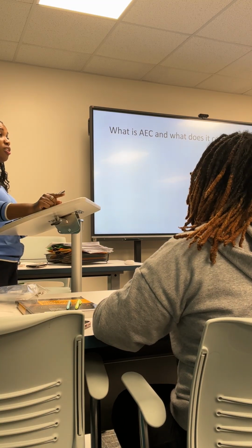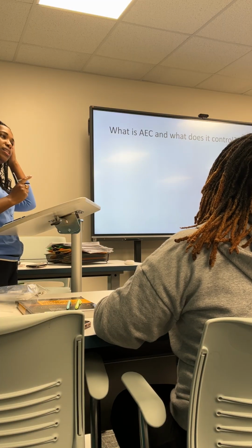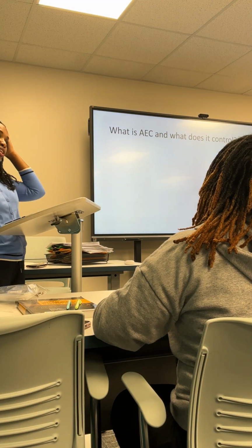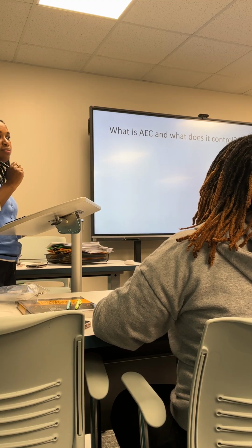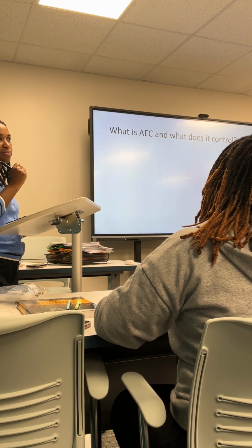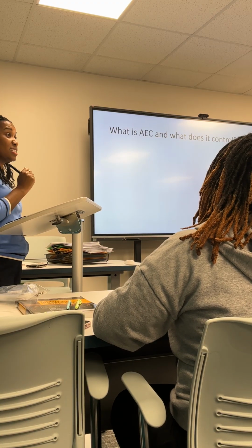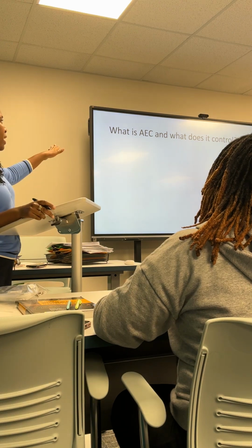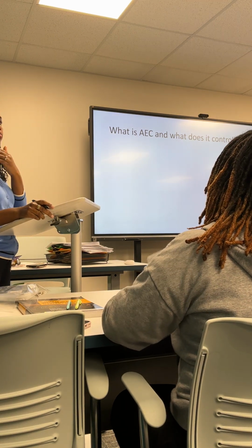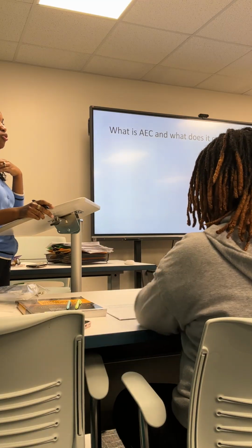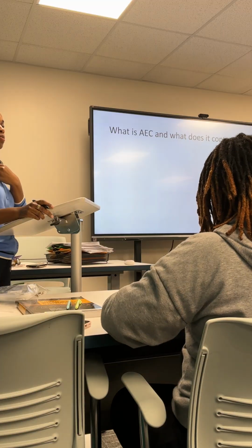Automatic exposure control. So y'all are working together. It controls one thing really: exposure. MAs. So what part of the MAs? Y'all know it. Yeah, it's the S, the time. Okay. So write down AEC is automatic exposure control. It's a timing mechanism. It controls the time.